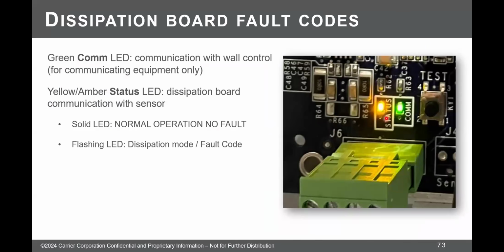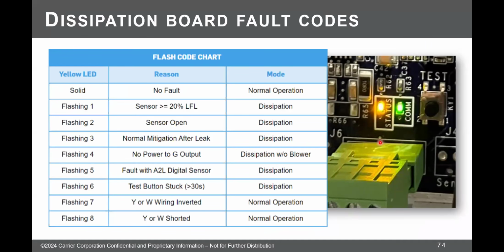As mentioned, there's alarm codes on the blinking yellow light. The green light is for the communicating systems. So you get two lights there. The yellow one is the one we normally pay attention to. For regular stuff, meaning residential and small commercial, there's 8 possible flash codes. I had mentioned specifically 1 flash, meaning there's a leak, 3 flashes, meaning we're finishing up to 5 bonus minutes of dissipation. But there are, in fact, other ones.